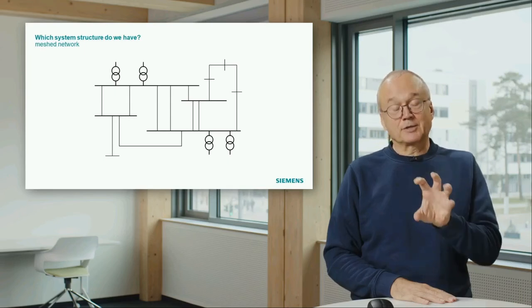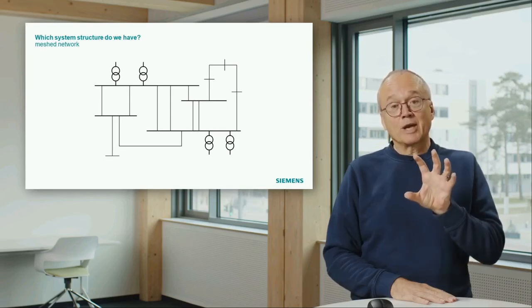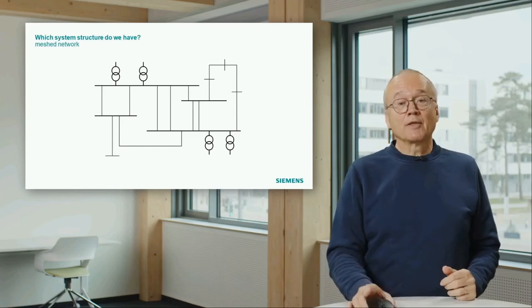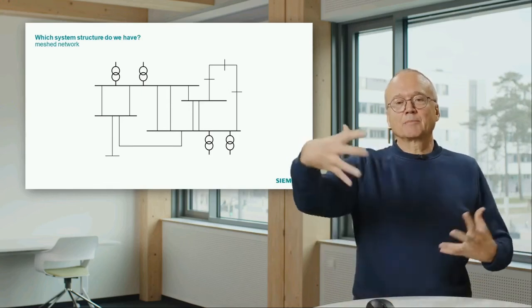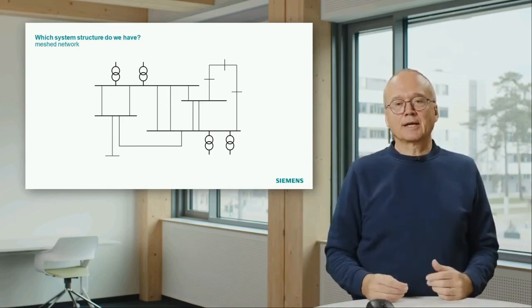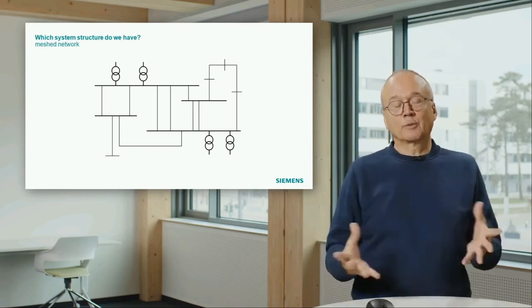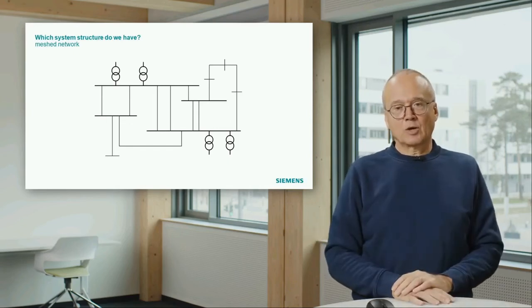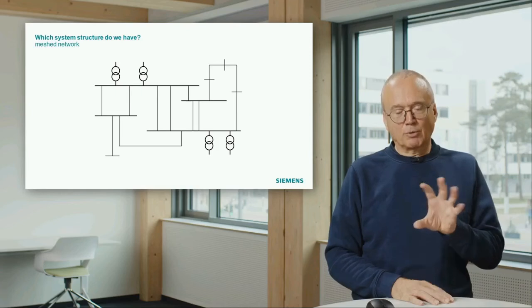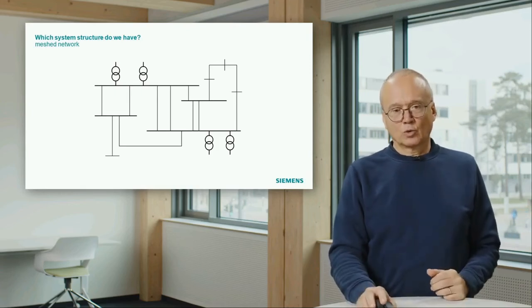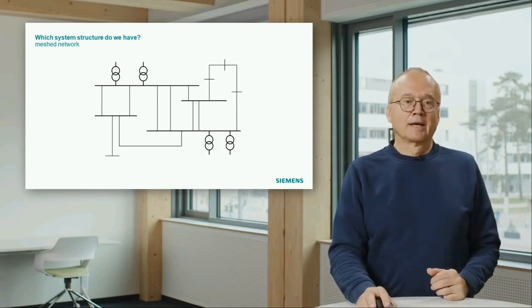An important thing for protection is that we have a meshed structure. That means if we have a short circuit somewhere on one line, the current comes from different sides, from different directions, into our line. And that is an important fact to define the protection.